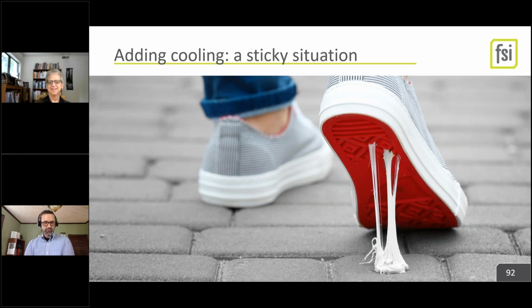Adding cooling, just tacking onto an existing system, pushes you into so many code requirements that it's not something you just say, oh yeah, I'm just going to add some cooling. It's fine. It's going to trigger, like Duane said, possibly envelope upgrades to do such a thing. You might be touching systems that don't have anything to do with cooling. And it also opens up a bunch of mechanical Pandora's box with those economizer provisions - can you even meet that requirement in your particular building layout that was never intended to have cooling? So that's something to get deep into really early in design. If that's something you want to do, go talk to some mechanical engineers before you really get deep into it.